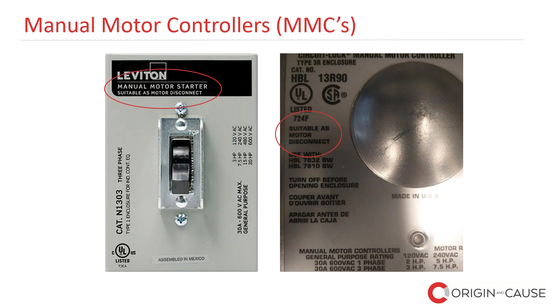One of these is a case study of a maintenance worker who was intending to maintain a pump motor and to replace it, in fact, when he found that it wasn't functioning properly. But he used a manual motor controller to disconnect. Unfortunately, the line side of the motor disconnect was welded, the contacts were welded shut, so energy remained in the pump motor. And when the worker didn't test for energization and went to work on the motor, he was electrocuted.